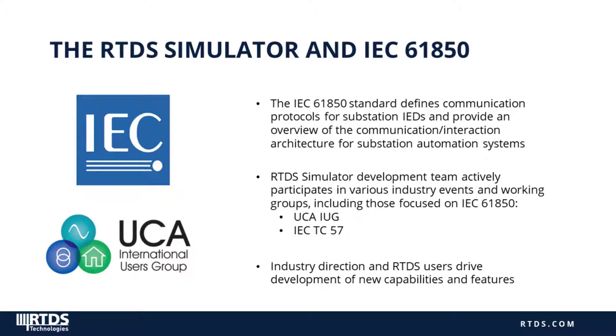The IEC 61850 standard is an increasingly important component of modern protection systems, and thus of protection testing. The standard defines communication protocols for substation IEDs and provides an overview of the communication architecture for substation automation systems. Around 2010, RTDS Technologies released its GTNet capabilities to allow users to incorporate IEC 61850-compliant devices into the closed-loop testing process. Our protection and automation team participates actively in industry working groups such as the UCA International Users Group and IEC Technical Committee 57, focused on the 61850 standard. Changes to the standard, to commercially available protection devices, and user requirements are all driving RTDS developments in this category.